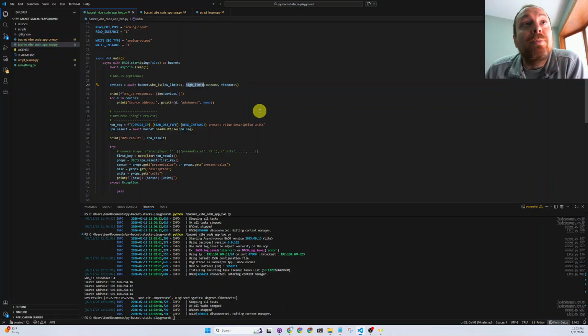And also, there's a lot of old buildings out there where some of these devices are not BACnet over IP. They're BACnet over a 2-wire network called master-slave token pass, BACnet over MSTP. It's an older, cheaper technology, RS-485 it's called, like Modbus over RTU is an RS-485 network, a 2-wire twisted pair network.